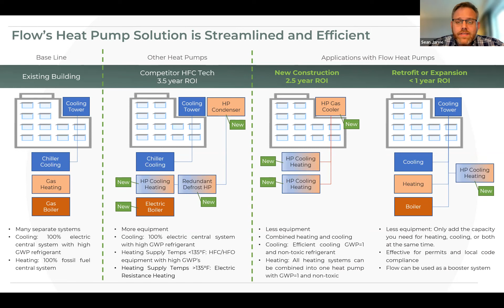So a lot of times in this electrification and decarbonization movement, we have a problem with not having enough power. Even in new construction, there's not enough utility coming to a lot of these sites, but there is enough to run a chiller. So if you substitute that chiller out with a new CO2 chiller that can also do heating, now you have the exact same power utilization, because they are equivalent in overall efficiency and capacity. You don't have to bring in new feeds. You can get rid of that boiler as needed, or change it out and leave it in place as a backup, for instance, and make two different heating sources, one for your low temperature hydronics or your domestic hot water heating, and another for your boiler modes or your in-floor heat, or whatever your system might want to do. And that makes some of these retrofits just simply amazing. And so payback is almost immediate in those cases.